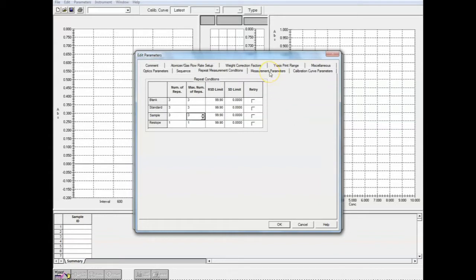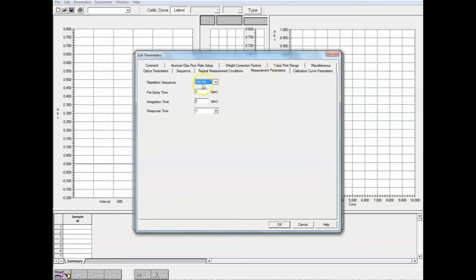Under measurement parameters, this repetition sequence refers to what the machine actually does when it takes a measurement. We have 2 options. S and M are for spray and measure. Spray, measure, measure, measure means that with 1 spray into the machine, it will take 3 consecutive measurements from that same sample. We could do the opposite, which would be to take a spray and then a measure and then another spray and then measure and so on. We want it to do 3 measurements on 1 spray, so we're going to change that to spray, measure, measure, measure. Everything else stays the same.